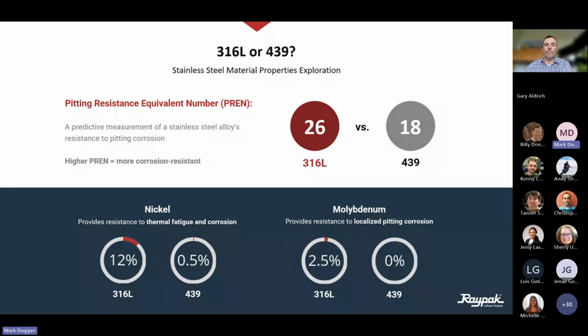The reason for that being is the 316L has a little bit more nickel, which provides resistance to thermal fatigue and corrosion. So you can see here, 316L stainless steel has 12% nickel, whereas that 439 only has 0.5% nickel. The other nice thing is we've got a little bit more molybdenum, so that molybdenum provides resistance to localized pitting corrosion. 316L stainless steel has 2.5% molybdenum, whereas 439 has 0. So, overall, stainless steel in general is a pretty weak metal. The only reason we like to use it on our condensing boilers is it's the only thing that can handle condensate. So having that stronger material in the stainless steel just provides longevity for the boiler, prevents that thermal fatigue, prevents corrosion, and just like I said, it helps with the longevity of that fire tube heat exchanger.